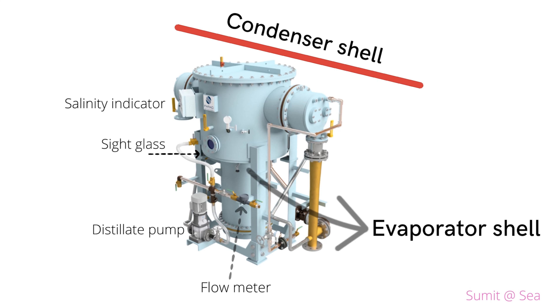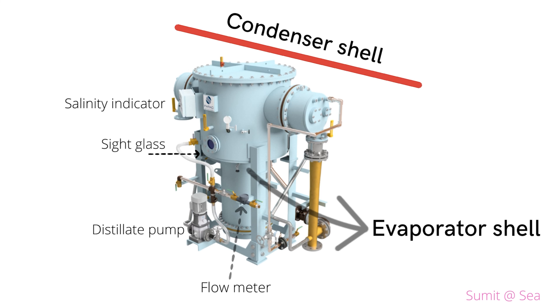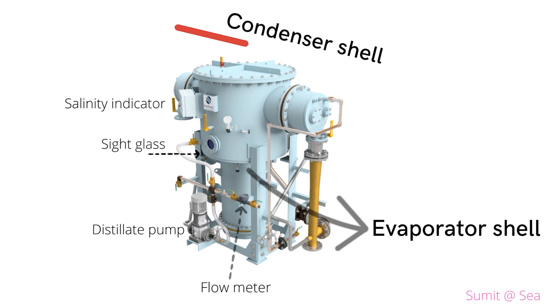The desalted vapors then pass through and come in contact with the condenser, where they are condensed by means of incoming cold seawater. The distilled water is then taken out by the distillate pump, controlled by a salinometer and solenoid valve, and later transferred to the fresh water tanks.